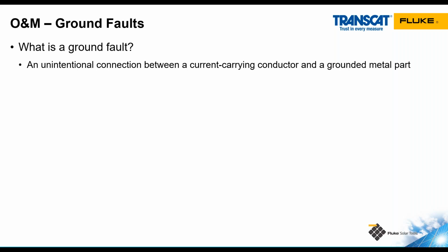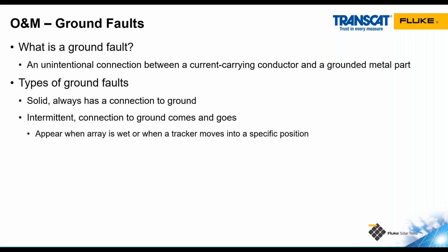A problem that we run into relatively frequently in solar is called a ground fault. The ground fault is an unintentional connection between a current carrying conductor, like our DC positive or negative, and a non-current carrying metal part, like our module frame, racking, conduit, metal junction boxes or inverter cases. There's two main types of ground faults. A solid ground fault is a low resistance connection that is always present. Those are relatively easy to find.